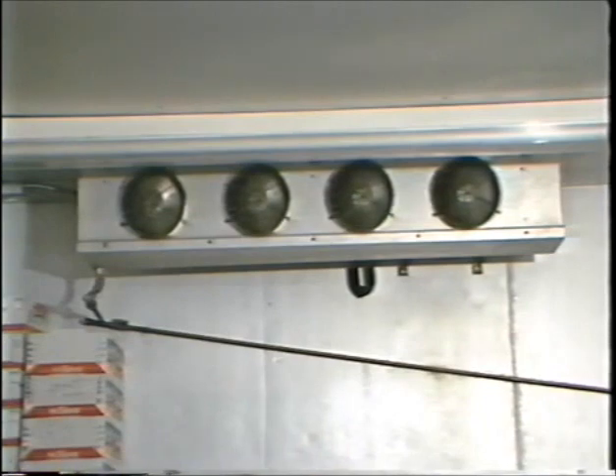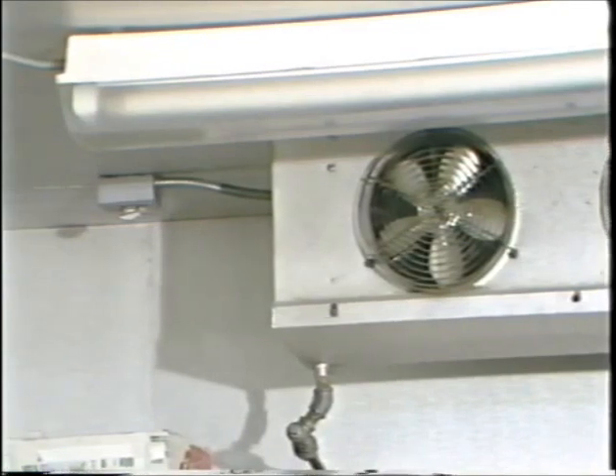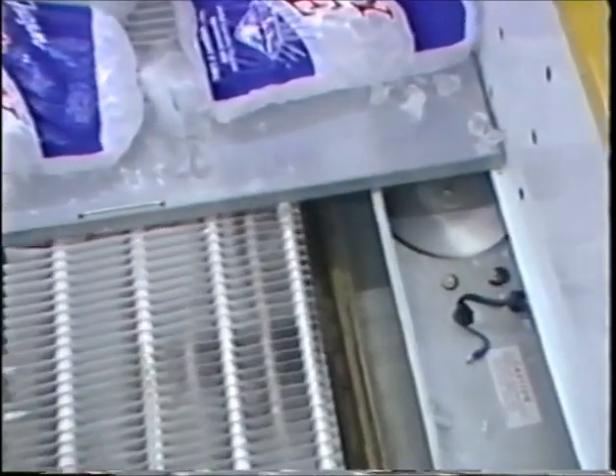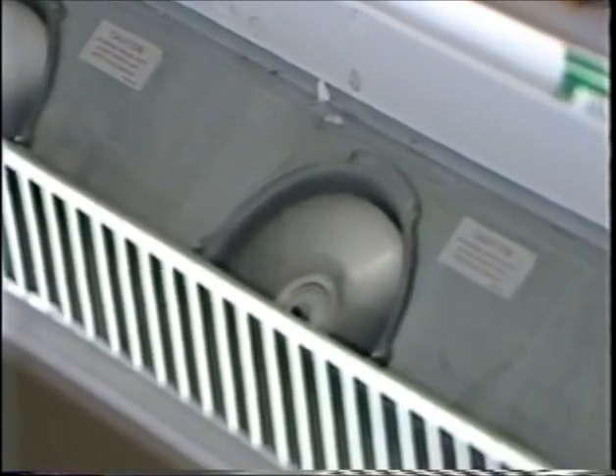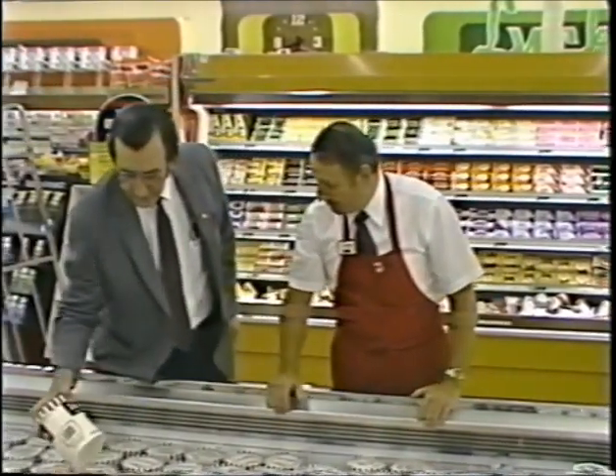The cooler box coil should be kept clear of dust and caked-on dirt. To clean these coils, turn off the switch at the coil, or in some cases disconnect the twist lock plug from the electrical receptacle. Remove dust and dirt with water and a mild detergent. After cleaning the coil, turn on the switch or reconnect the twist lock plug. Fans are used extensively in refrigeration systems — be on the lookout for malfunctions. During the life of a display fixture or blower coil, it's possible that a fan blade can become damaged, that bearings become worn, or the motor burns out. Notify your store manager if you hear odd fan noises such as rattling, whining, or grinding sounds, because these are the usual indications of fan failure.